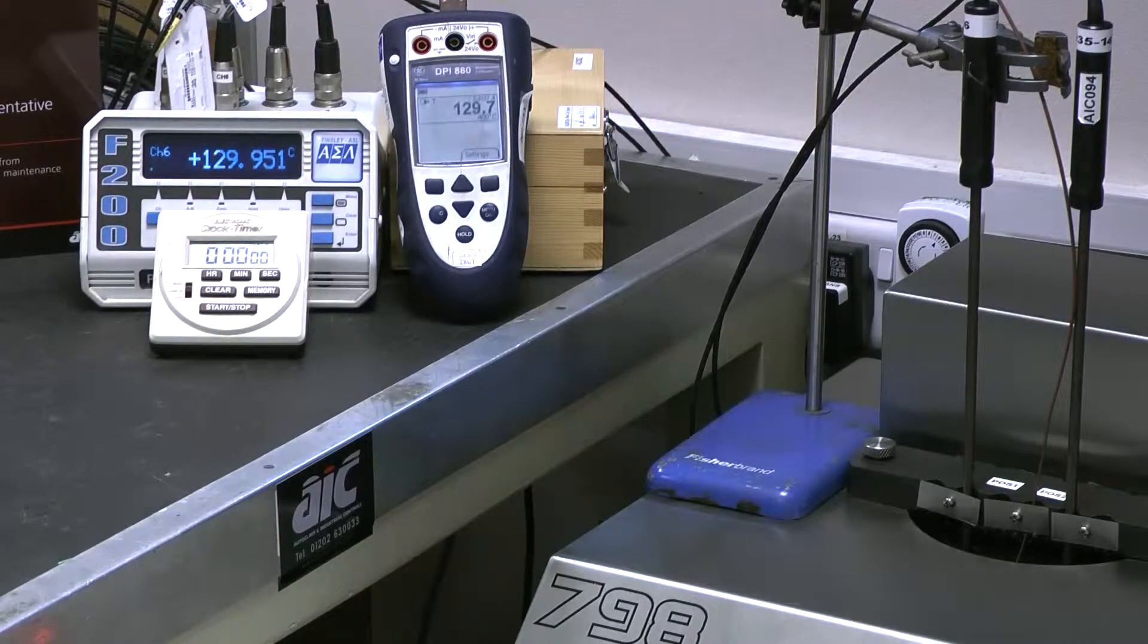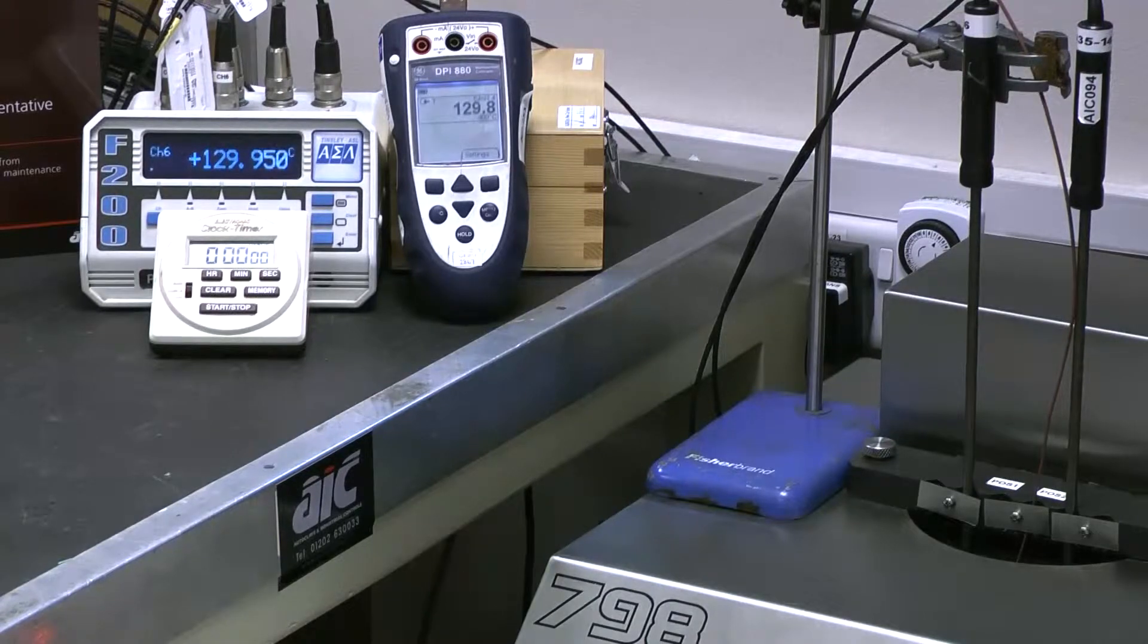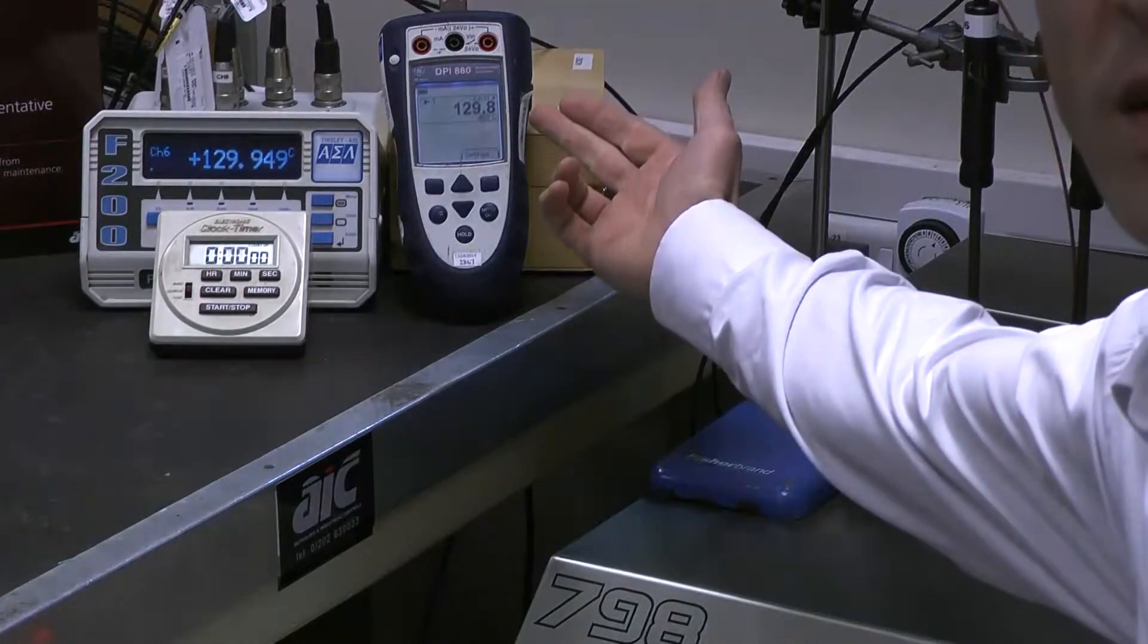So all appears to be well. The oil is at 129.9 degrees, and we're reading about 129.9 on the process calibrator here.